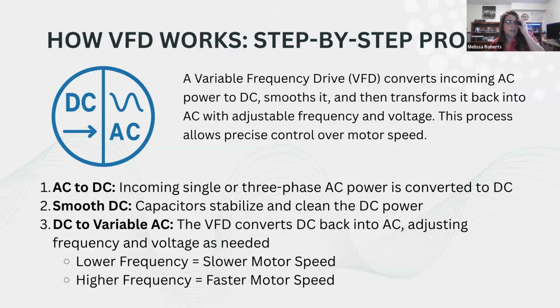So how a VFD works, step-by-step: it converts incoming AC power to DC power, smooths it, and then transforms it back into AC with adjustable frequency and voltage. This is the process that allows precise control over motor speed. So incoming single or three-phase AC power is converted to DC, then capacitors stabilize and clean that DC power, and then it's converted back into AC, allowing for adjustable frequency and voltage as needed.